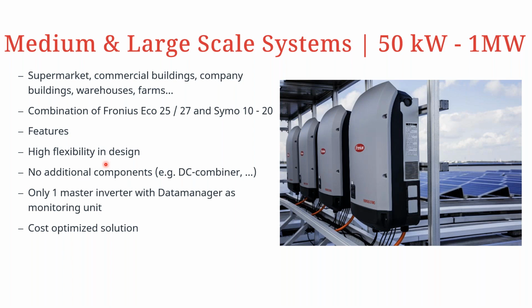And you can conveniently combine the Fronius Eco 25 to 27 and the Fronius Symo 10 to 20 kilowatts. That gives you a lot of flexibility because, like we said before, with the Superflex design capability, you can integrate a lot of different orientations by mixing the Fronius Symo and the Fronius Eco in one setup. So if you do it with a direct connection, as we can see in this particular picture, you do not need extra components such as DC combiner boxes. So you can get some savings there.